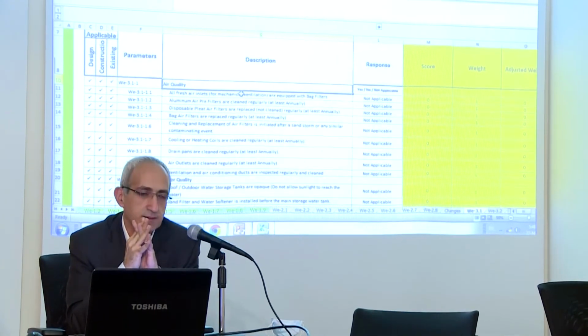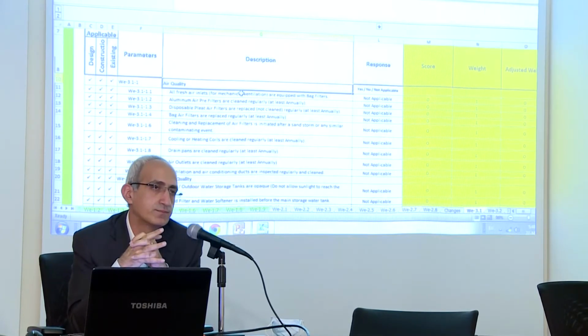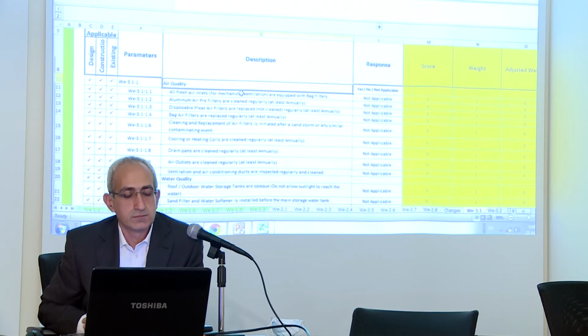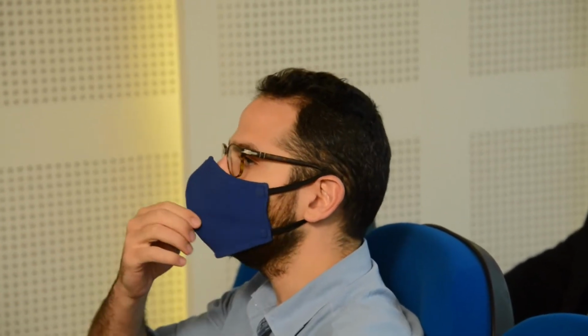We have finished this criteria. If anyone has some questions. Okay, one question. The first requirement was that all fresh air fans need a bag filter. So I have, I guess, one remark on the header sheet. And every time we put a bag filter on a fan, the motor of the fan is going to become bigger because there's a lot more pressure drop on the fan. I understand why it's there, but I was wondering, is there an alternative or should we put a limit? That if a fresh air fan is above a certain flow, it must have a bag filter because there's a lot of fresh air being brought in. But if it's this and smaller, then not.